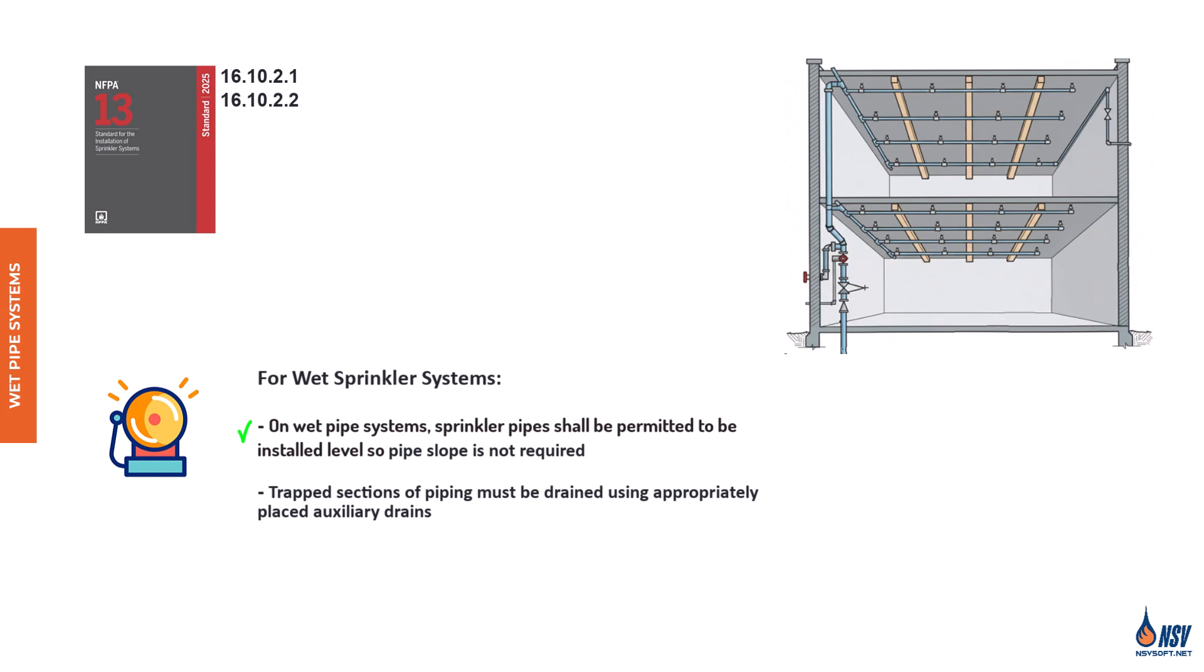Section 16.10.2.2 emphasizes that any trapped piping must be drained. This means auxiliary drains must be provided to ensure complete drainage of isolated pipe sections. In summary, while pipe slope is not required for wet systems, proper planning for auxiliary drainage is essential to maintain system integrity and prevent water accumulation.